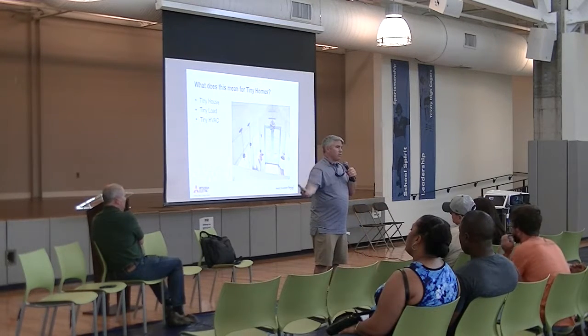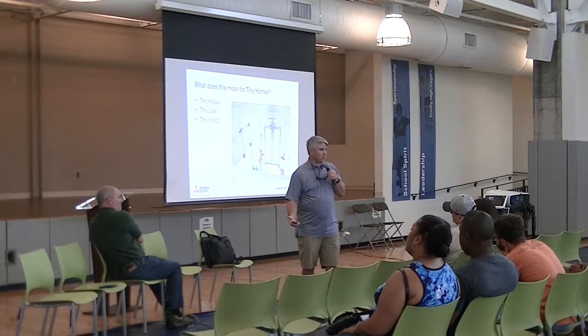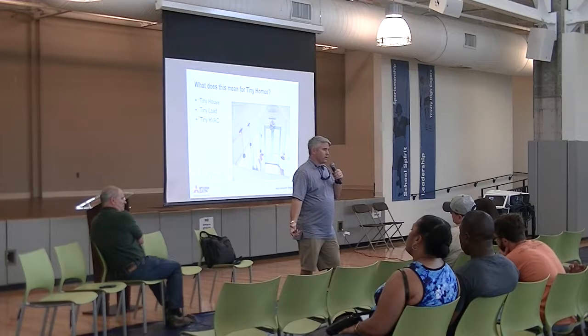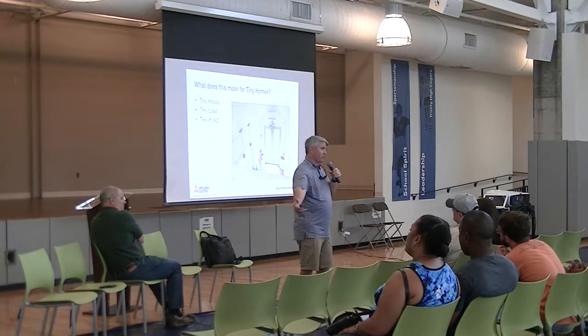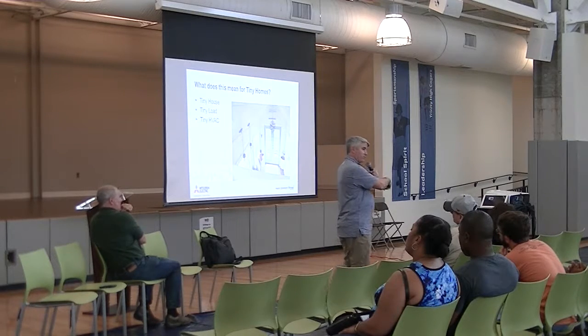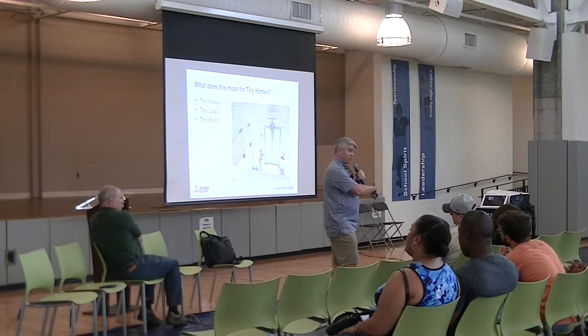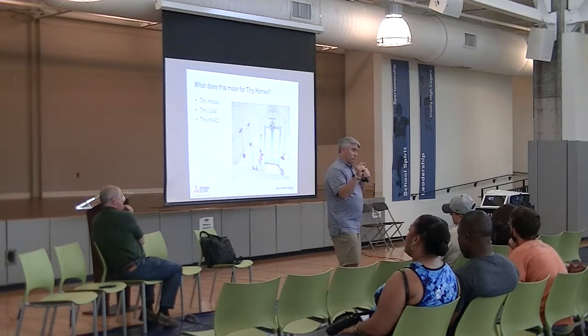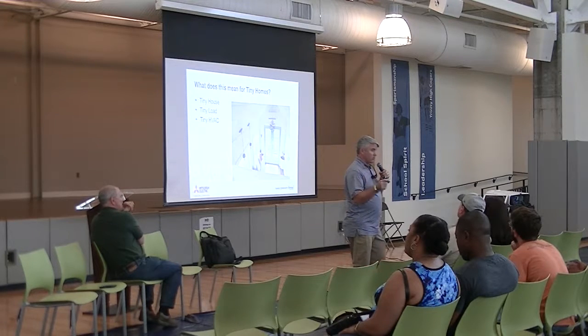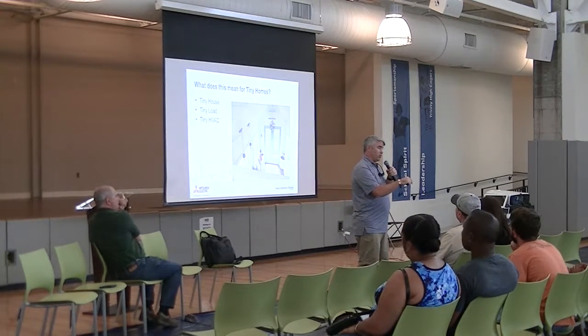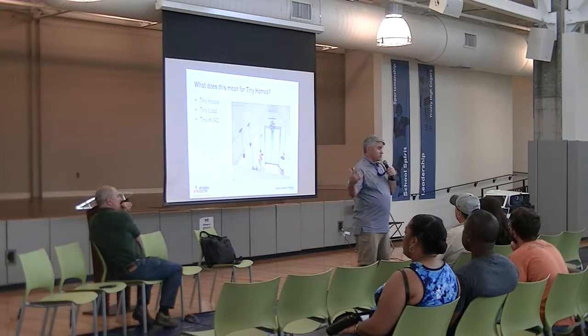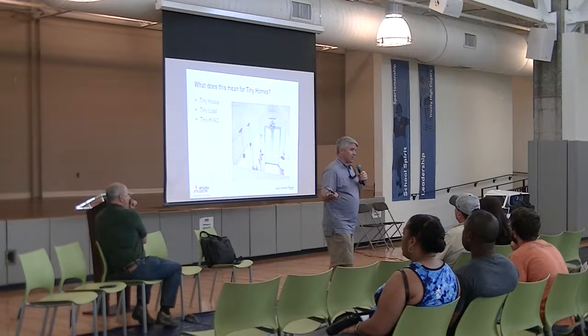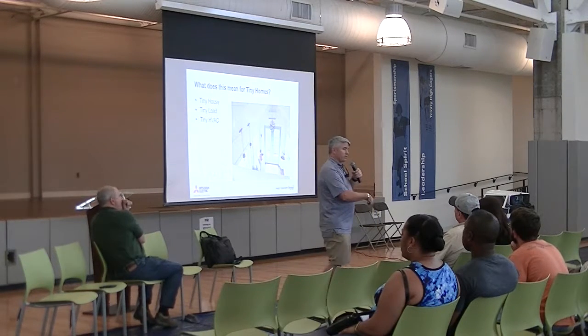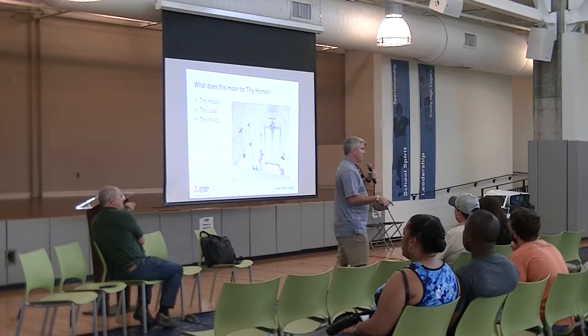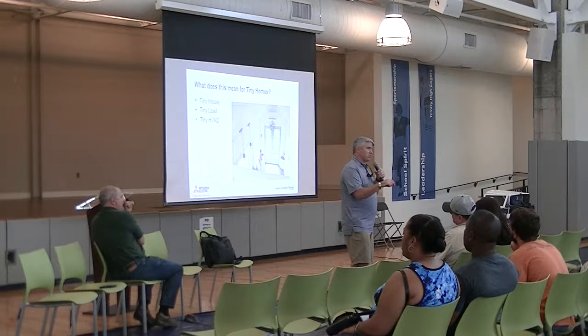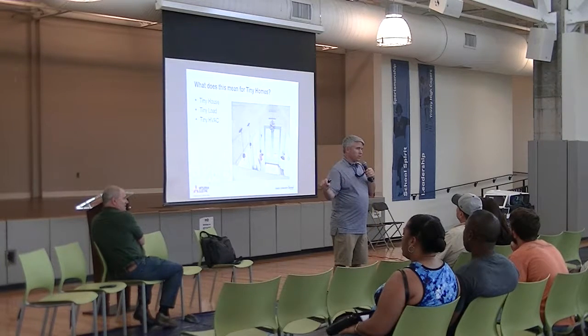An average size home, let's say 2,000 square feet, might have a heating and cooling load of 2 tons, or 24,000 BTUs. But what about a 400 square foot house, or a 150 square foot house? We're talking about micro loads. Suddenly it's a real challenge to pick HVAC equipment that can go that low, because the smallest conventional heat pump is 18,000 BTUs—a ton and a half. 12,000 BTUs is a ton of heating or air conditioning. So if the smallest conventional system is 18,000 BTUs, is that going to be oversized for a tiny house?